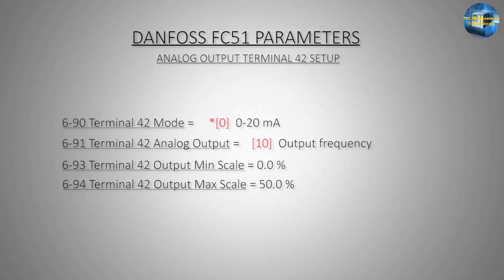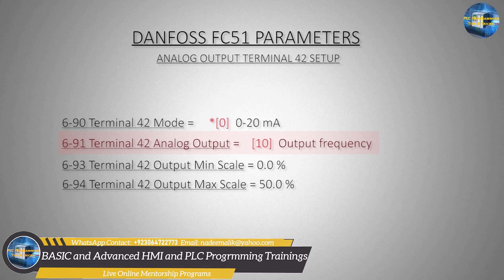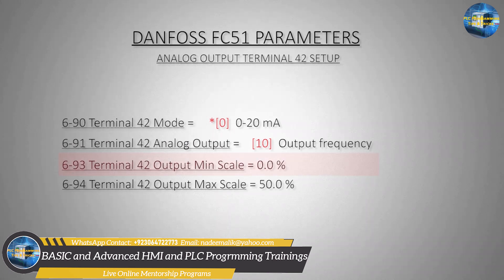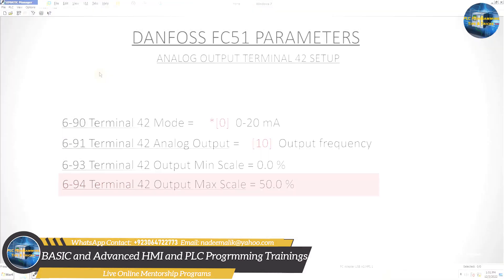Next we will set up parameters for the analog output terminal 42 of the VFD, which will be used to send an analog signal back to the PLC. We set parameter 6-90 to 0, which sets the output signal range as 0 to 20 mA. Next we set parameter 6-91 to 10 — now this terminal will send an analog output signal from 0 to 20 mA proportional to the output frequency of the VFD. We scale the analog output minimum as 0.0% and maximum as 50.0% using parameters 6-93 and 6-94. For more details on these scaling parameters, refer to the Danfoss FC51 VFD user manual.